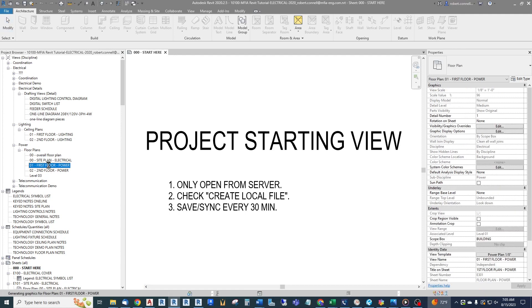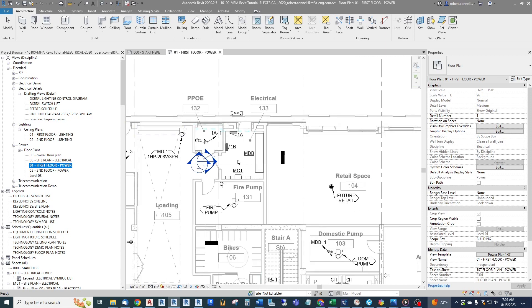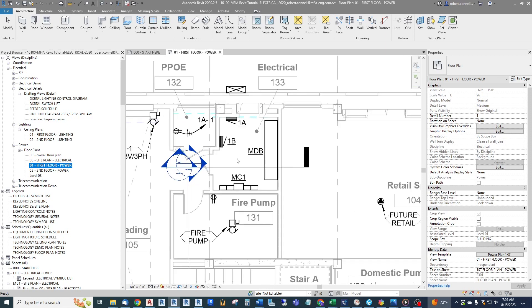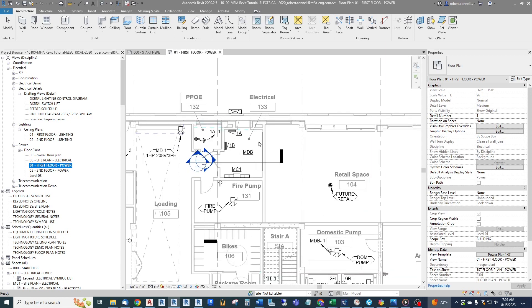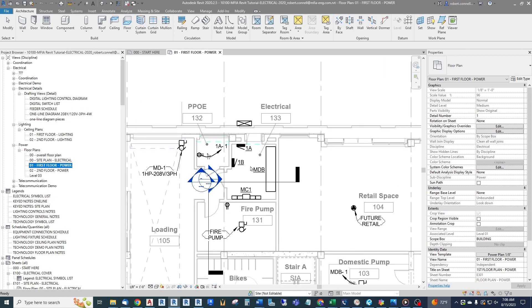On the first floor power plan, in the electrical room we have a main distribution board, two branch panels 1A and 1B, and a meter center MC1. This entire building is 120/208 three-phase — we do not have any 480, so no transformers within our building. That's a different subject. For this one we're just going to look at the 208 system getting interconnected. Some people start at the utility connection — the utility has a transformer that could be in a street vault, pad mount, on poles, or in a vault within the building.